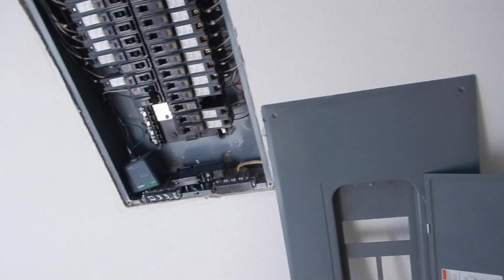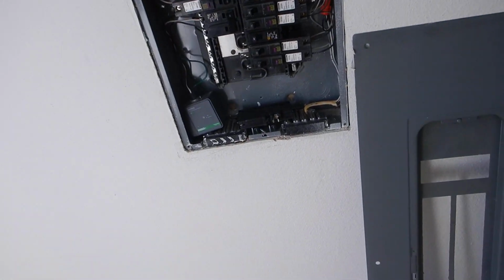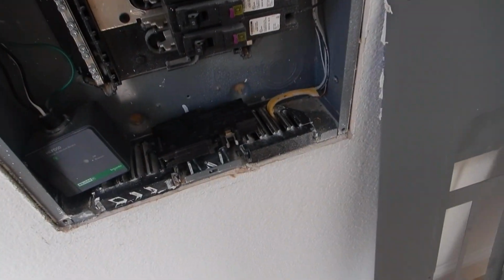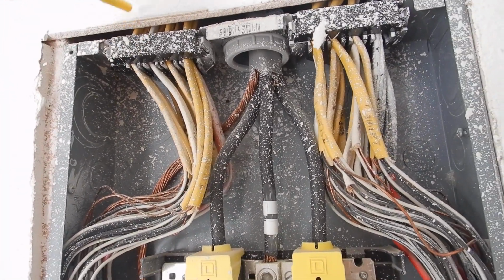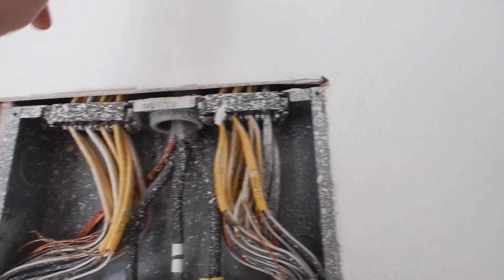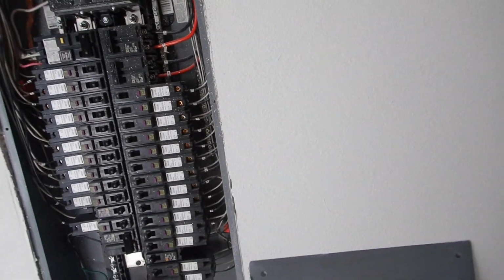This cabinet was put in with screws. Screws can pop out and break. If this house was to experience a tornado or something like that, you've already got a bad day. I get that. But it would have been better if they hadn't put screws in there. We're not supposed to have more than 1/8 of an inch gap between the cabinet and the wall. If this cabinet melts down, that's what keeps the fire from shooting out, burning up the paper, and starting other places, all kinds of stuff.